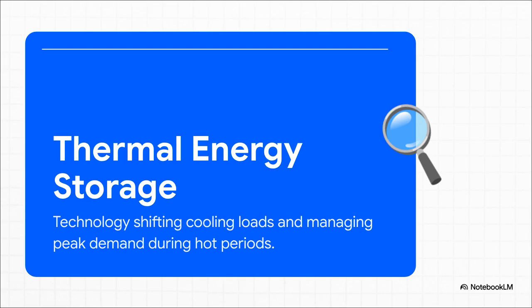This brings us to thermal energy storage, or TES, which is absolutely crucial here. TES allows the system to shift cooling loads and manage peak electrical demand. Think of it like a giant rechargeable battery for cooling. The central plant chills a massive reservoir of water overnight when power is cheap, and then deploys that thermal energy during the hottest parts of the day, taking serious pressure off the grid.